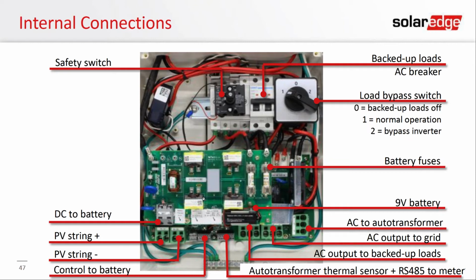Absolutely. So it still adheres to UL 1741, where we immediately disconnect from the utility in the event of a grid outage. And then using this auto transfer switch, we revert power to a backup load center. So a lot of questions about how do I create a backup load center. Basically, it's just a sub panel, and you're going to pull over some selected loads into the sub panel, and that's what you're going to back up.